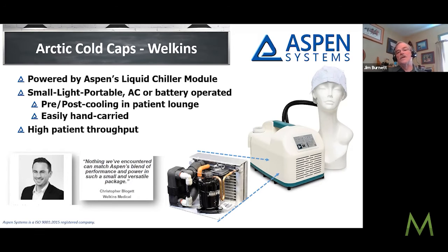The only way to achieve this is with an efficient refrigeration-type system that can run off a battery for a period of time. Thermoelectric cooling wouldn't work here because the cooling loads are too high and the power draw would be too much for the battery life. So there's a class of applications that need to go mobile, where we're creating new opportunities for medical device companies to take advantage of this technology.